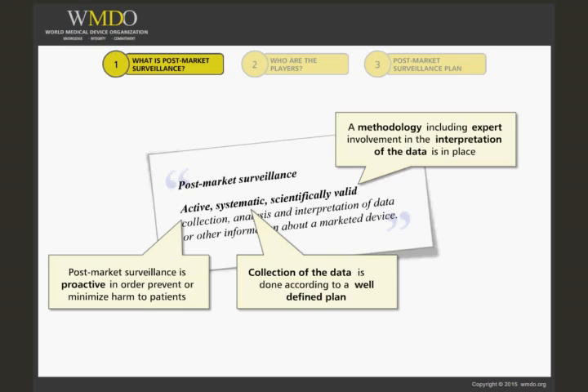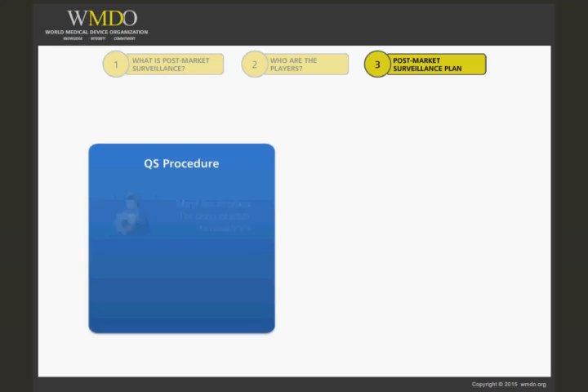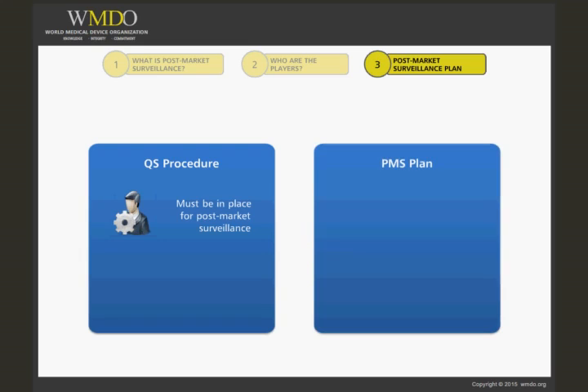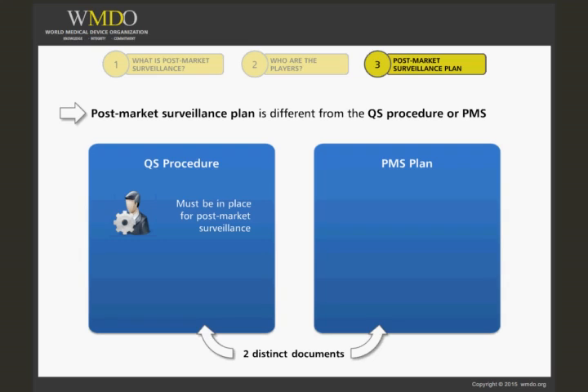For post-market surveillance, manufacturers are obliged to have a quality procedure in place in their company. This is not the post-market surveillance plan as such, since the plan is specific to the product and does not describe how operations in a company related to post-market surveillance should function. So the QS, or quality system procedure, and the post-market surveillance plan (PMS) are two distinct documents in your company, but both are needed.